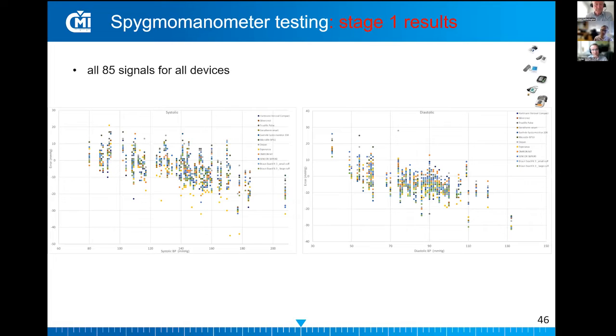If we display the test results a little bit differently in graphical form, we can see that a lot of results are within an acceptable region of, I would say, plus minus 10 millimeters of mercury. These are all results divided by systolic and diastolic blood pressures and the respective indication of the tested devices. We can say that a lot of devices performed quite well within certain blood pressure ranges. However, there were certain blood pressures where all devices produced faulty results. These faulty results were used in our second stage, which I will get to in a minute.